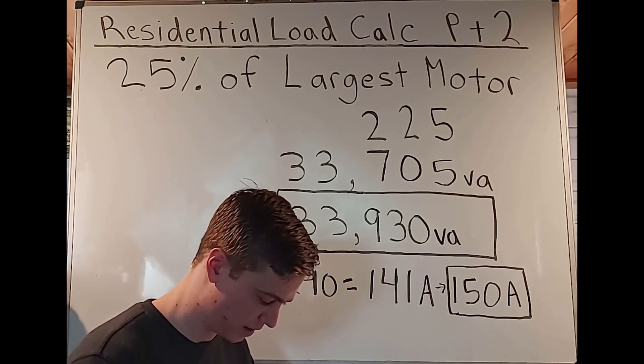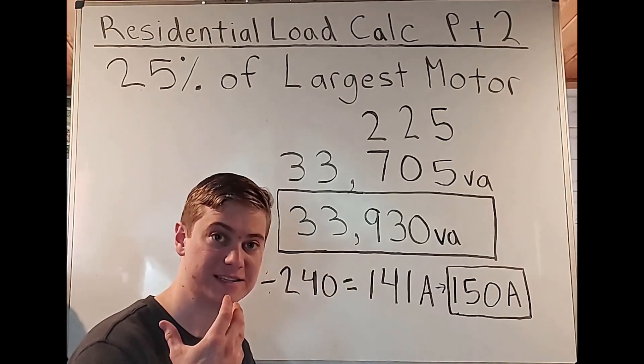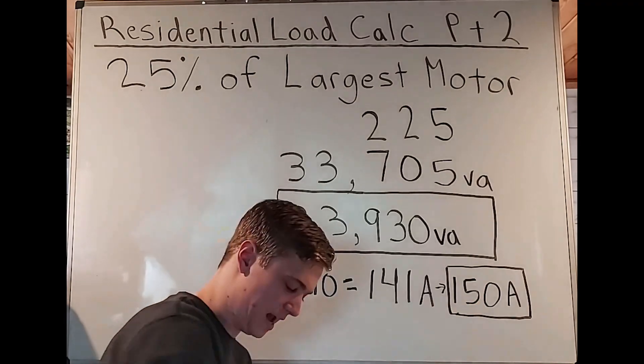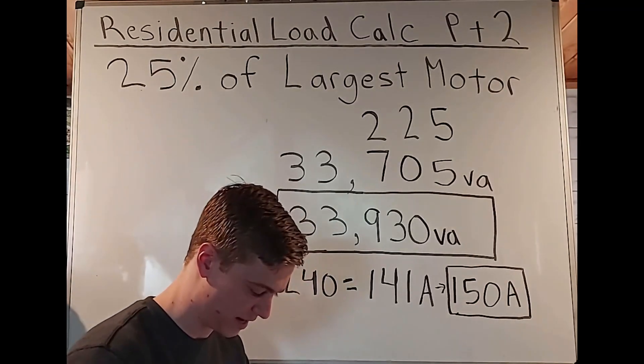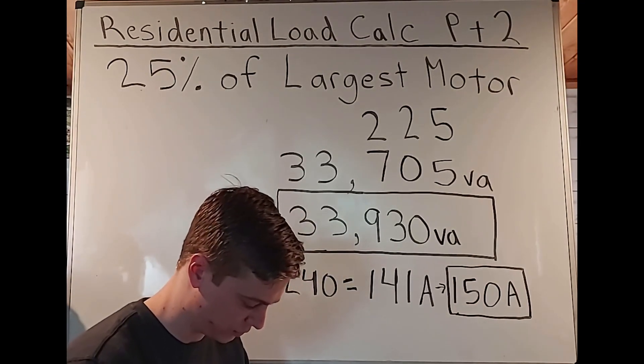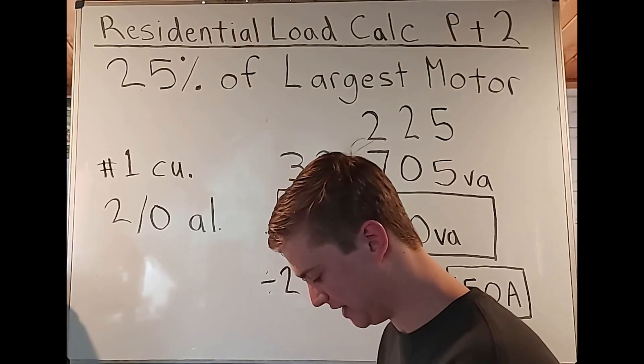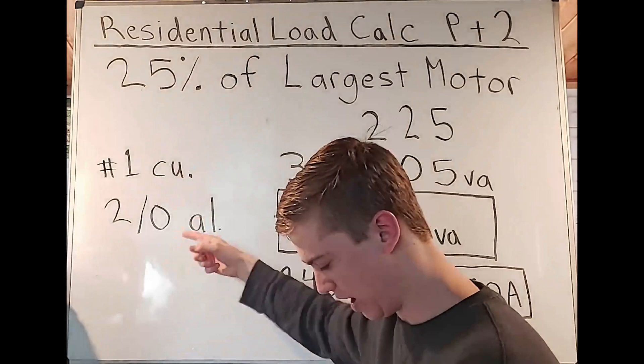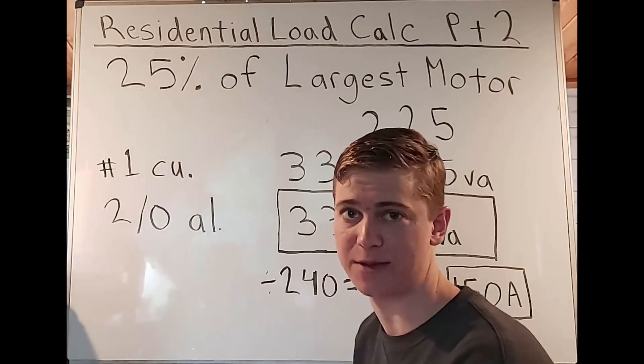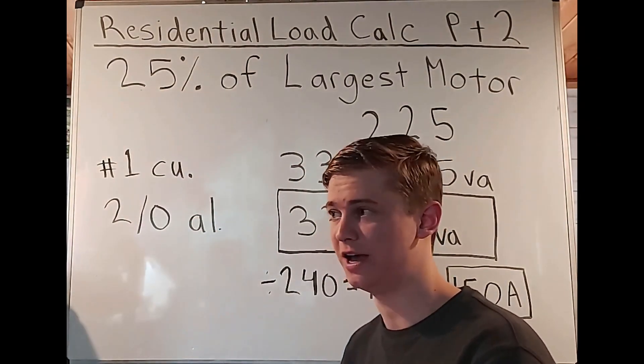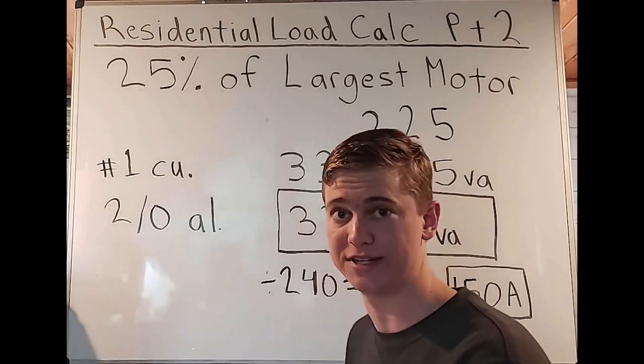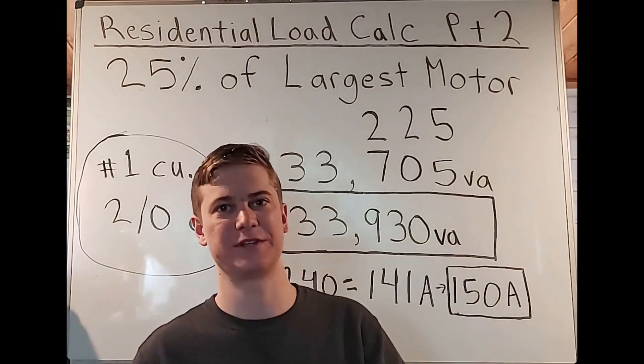So most of the time you're just going to be using table 310.12. We see it says single phase dwelling services and feeders. It goes all the way from 100 amps to 400 amps, because of course that is the limit for this table. We had a 150 amp breaker. That was the standard size. And of course we see that here in table 310.12. Now 150 amps is going to give us number one copper or two ought aluminum. And you can see that here in this table, you could also look it up on Google and you'll see, that's why you get that answer. That is not from table 310.16.